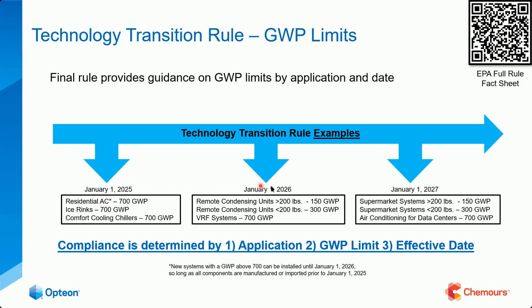This went into effect in 2025. This will go into effect in 2026. And this will go into effect in 2027. So let's walk through them. I'm going to start over on the left side. Starting January 1st of 2025, which is this year, residential AC can have no greater than 700 GWP. Ice rinks can have no greater than 700 GWP. Comfort cooling, no greater than 700 GWP. All right, moving to next year, January 1st of 2026, remote condensing units over 200 pounds can have no greater than 150 GWP. Remote condensing units with less can have more, up to 300 GWP. And then VRF systems will be 700, as it was before over here.